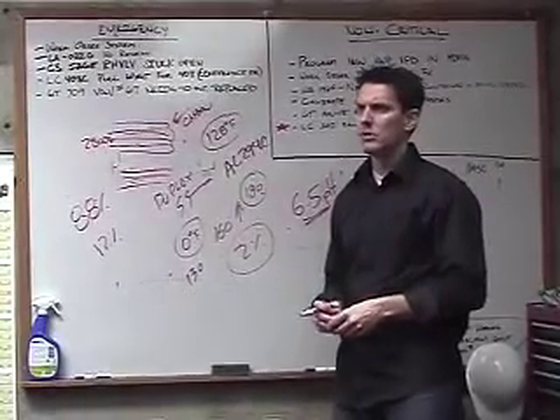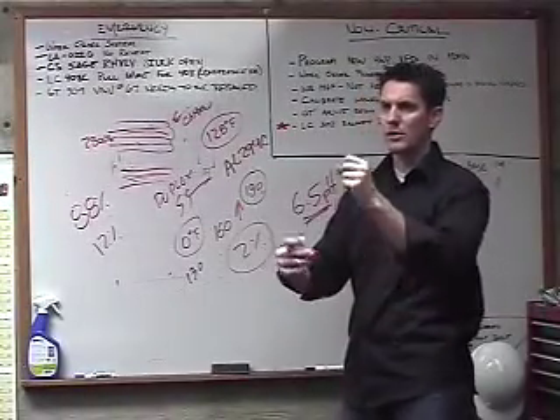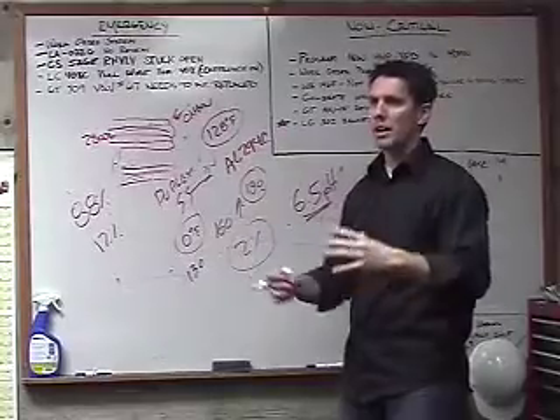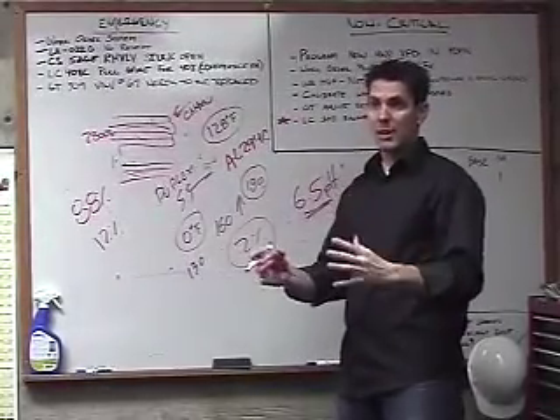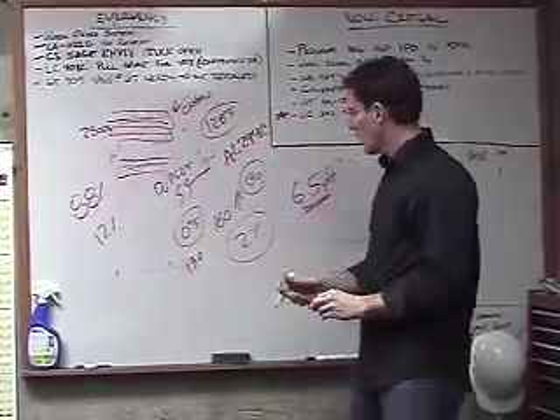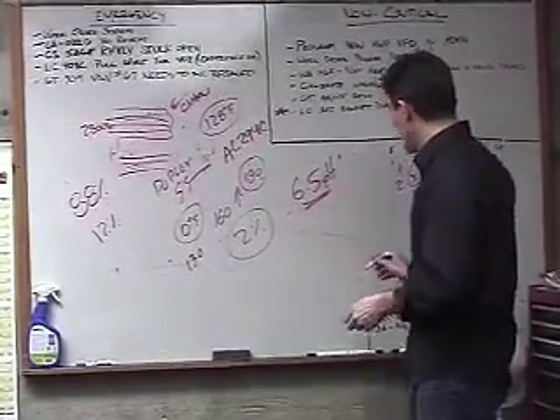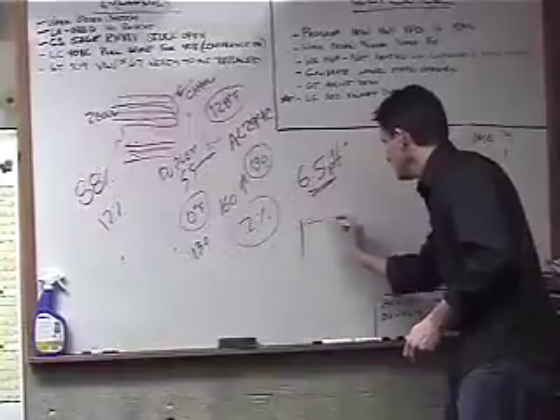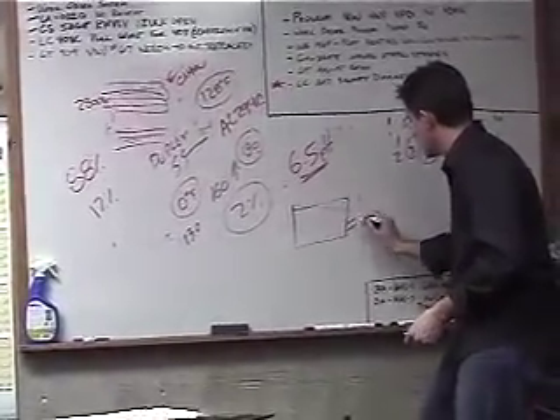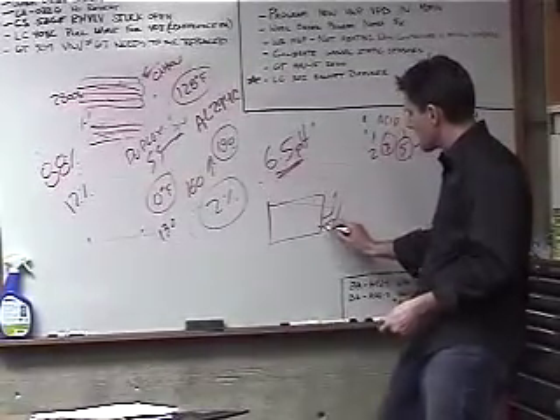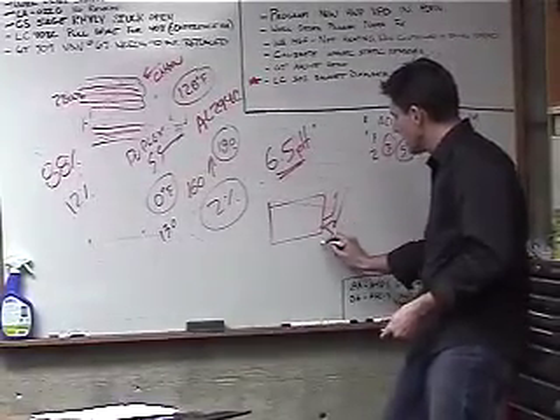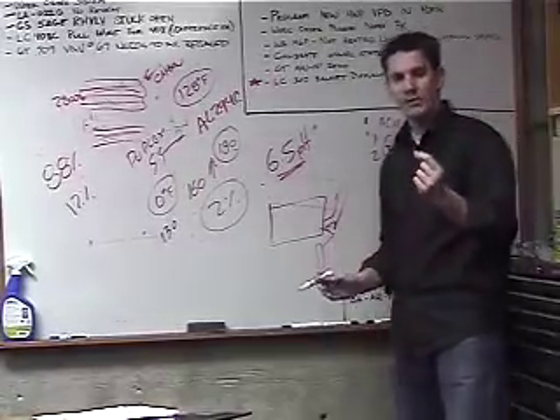What did we do? Did we do the little buckets, or did we do the little trap? Okay, so you guys have buckets that they can put the lime deposits in. Okay, so as we come off the boiler, well, I need to talk about that too. As we come off the back of the boiler, again, you've got your stack that takes off. We're bringing our acid out of the back of the boiler. And if you look at the back of our boilers, we run through one little bucket first.